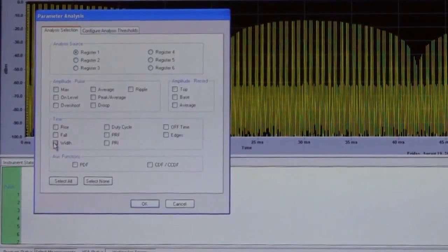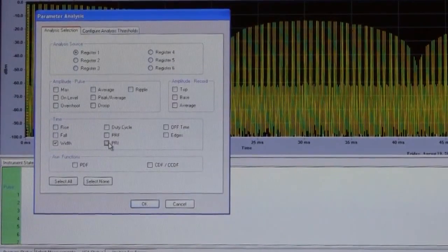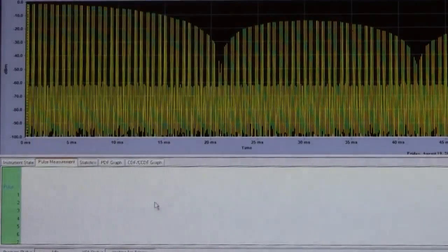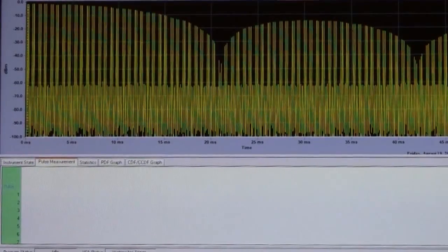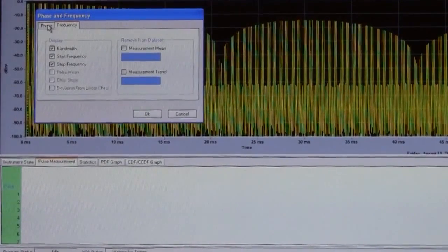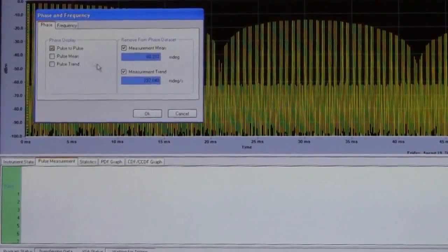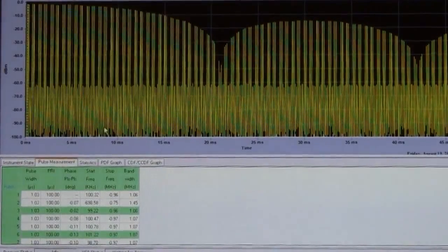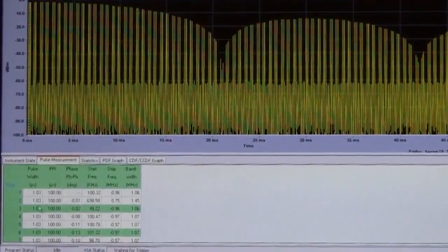Now we're going to add some analysis tools. For basic ones we're going to do width and PRI. Click OK. And then we're going to also do some frequency ones. We're going to do bandwidth of the signal. We're going to do start and stop frequency as well as the pulse to pulse phase of our signal. And you'll notice those displayed below here.